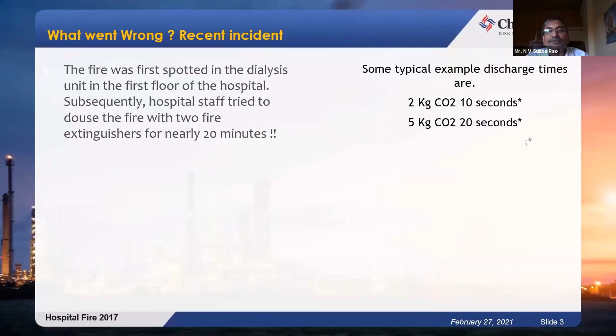To give a sense of the issues: in one hospital fire, the newspaper report said the fire extinguishers were used for 20 minutes. We wondered what they did for 20 minutes, because portable extinguishers have a maximum delivery time of around 40 seconds at best. Inside a hospital you may find a CO2 or DCP powder extinguisher with a maximum delivery time of 18 to 20 seconds. But these people said they fought the fire for 20 minutes using extinguishers, so that would mean bringing in a huge number of them.